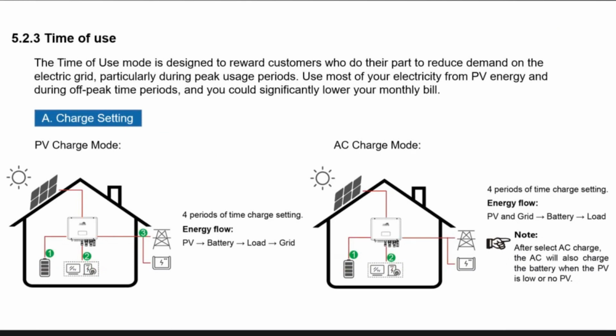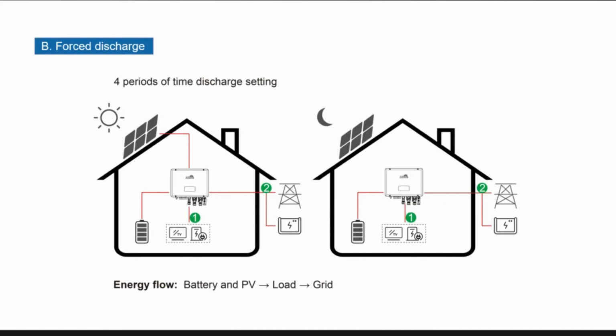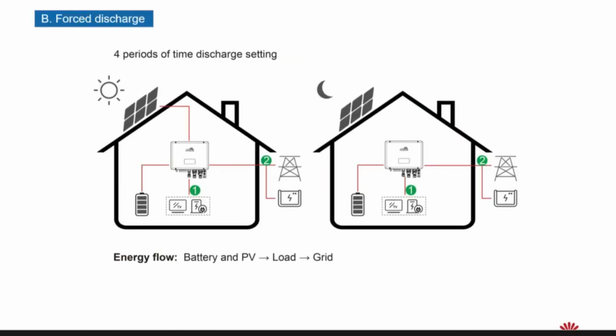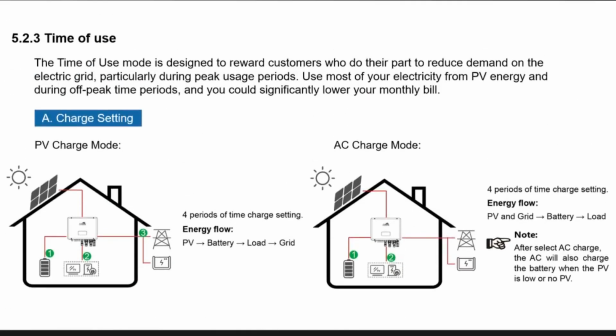If you have any questions, you can interrupt me and we discuss. For the time of use mode, we have three submenus. One is charging setting, where you can charge from the PV side and also from the AC side. Another is forced discharge. Another is forbidden discharge. This time of use mode is designed for customers who want to reduce demand on the grid, especially during the peak hour.